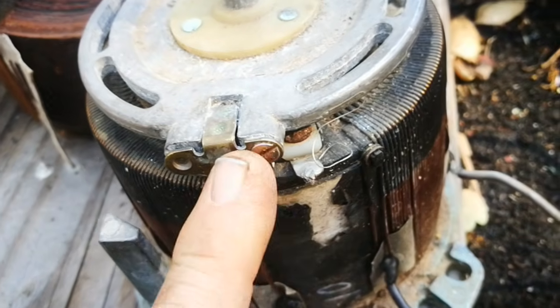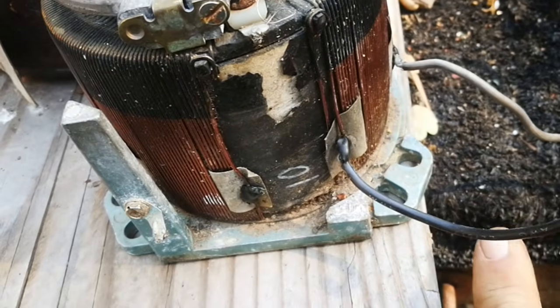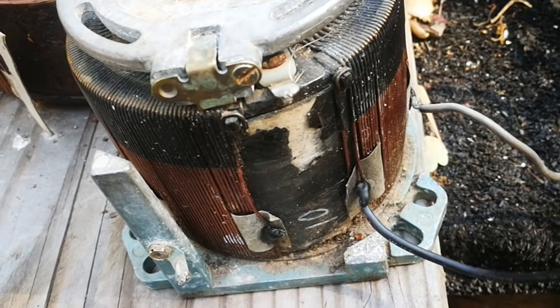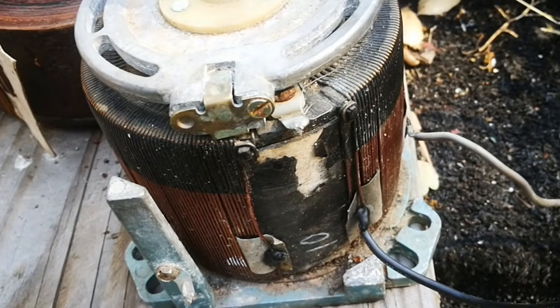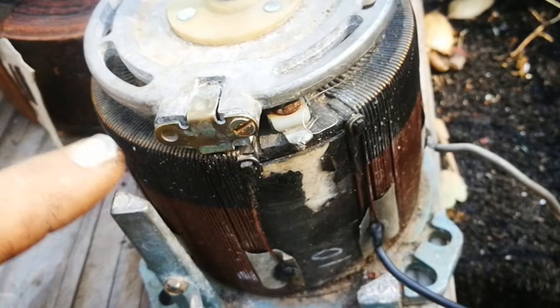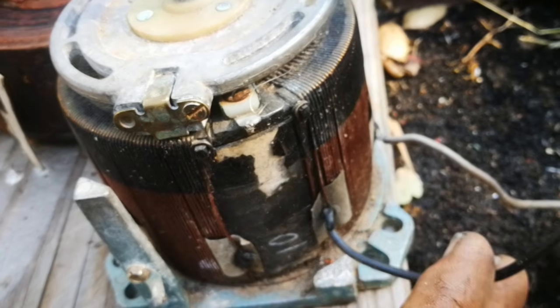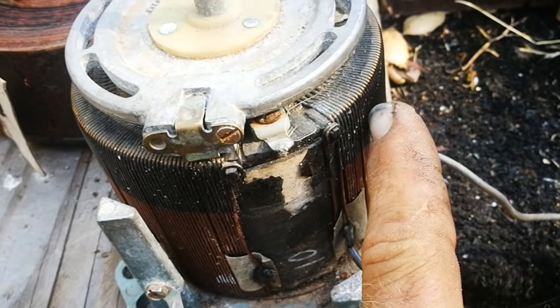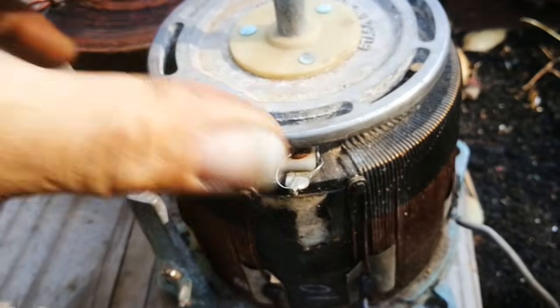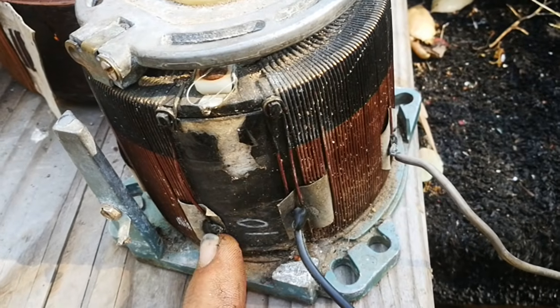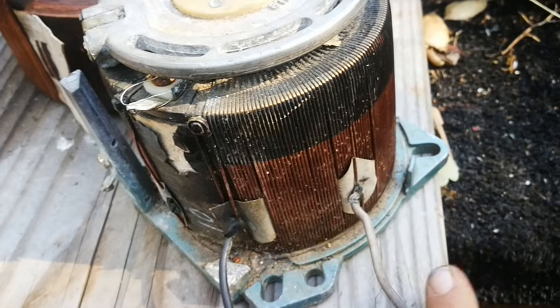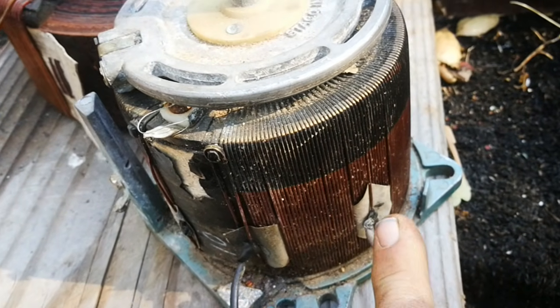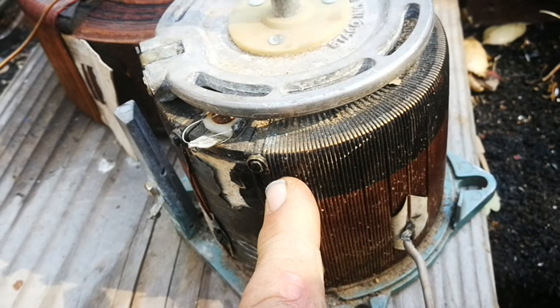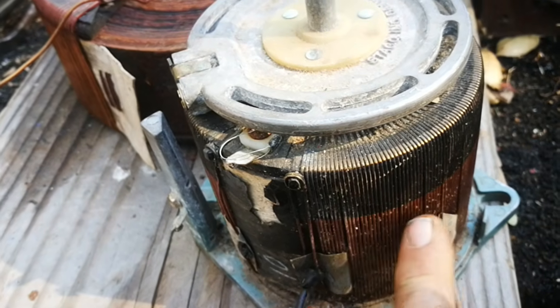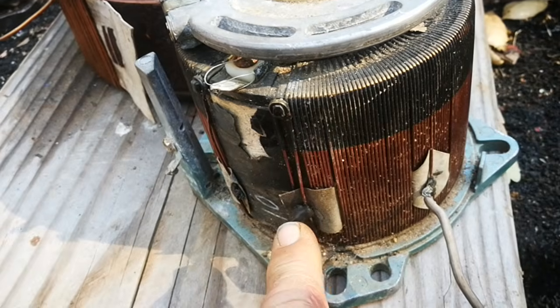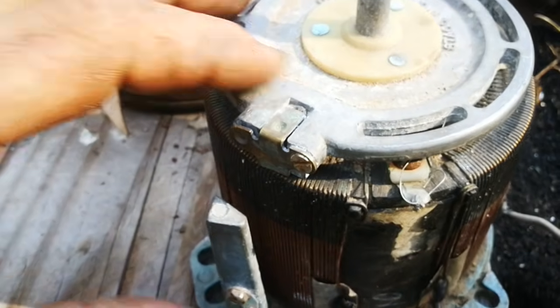If you have a wire going from this brush to an outlet, and one end of the 120 outlet to an output outlet, then by moving the brush along the surface of these coils, you can control how much voltage comes out, since the brush connects to the wires of the voltage circuit. If one end is connected here and the other at this point of the coil, you have extra coils to go past 120 volts, and you can pump the voltage up to 150 volts using those extra coils by connecting the other end here instead. That's how the Variac, or auto transformer, works.